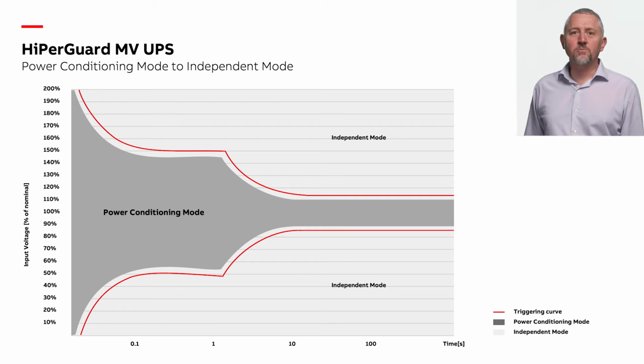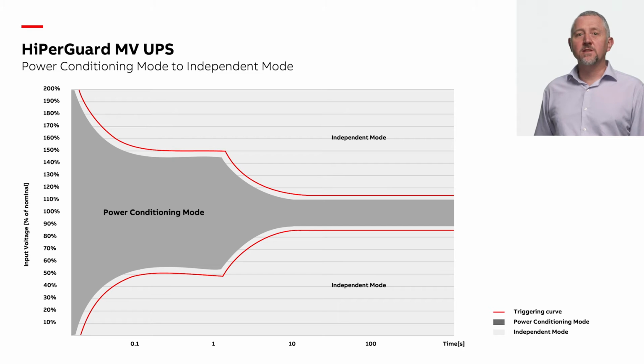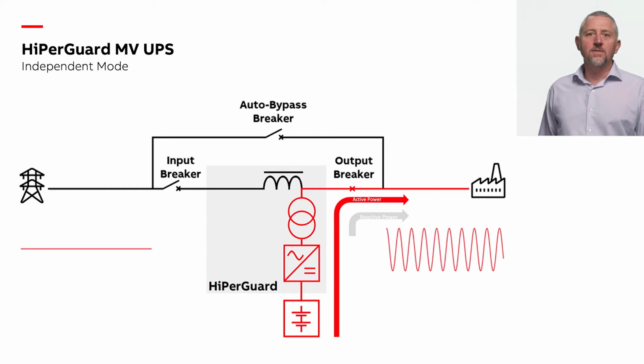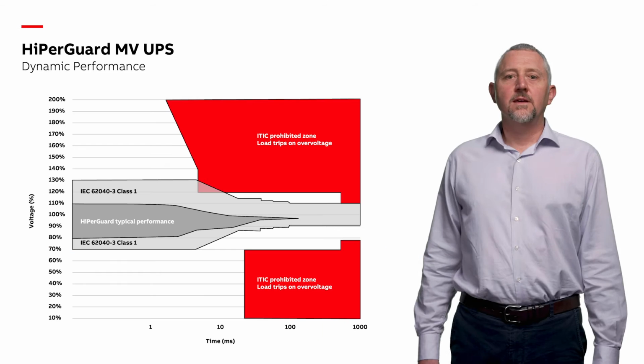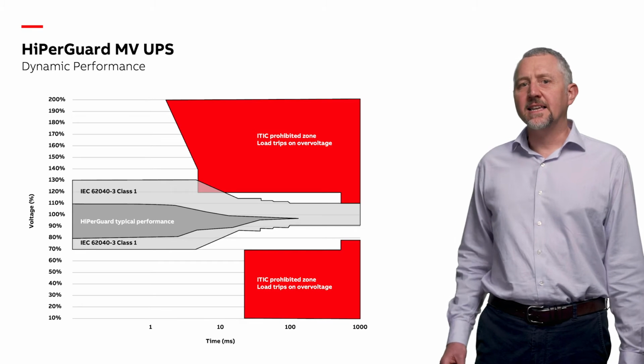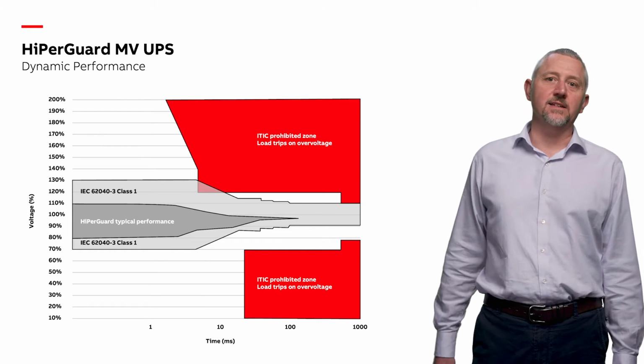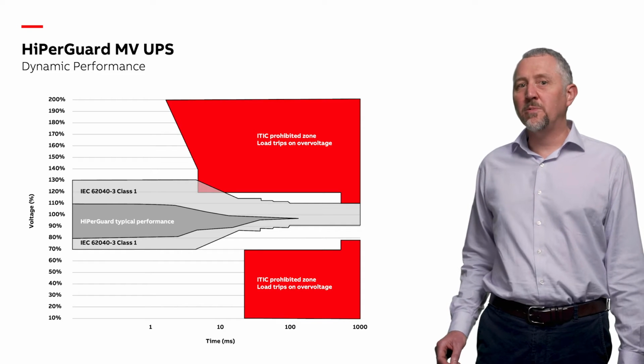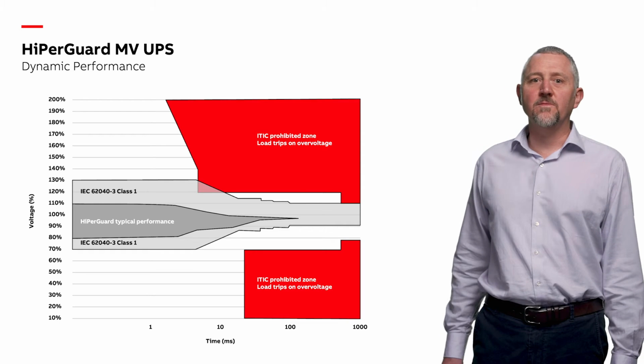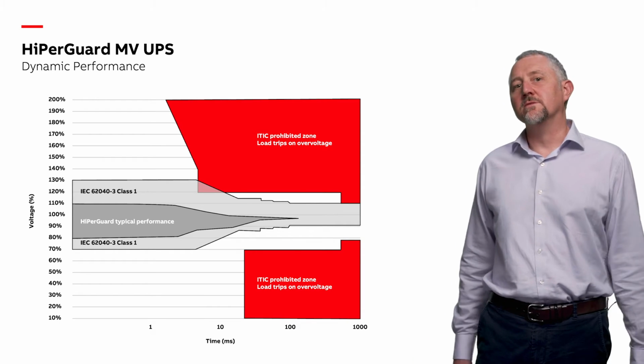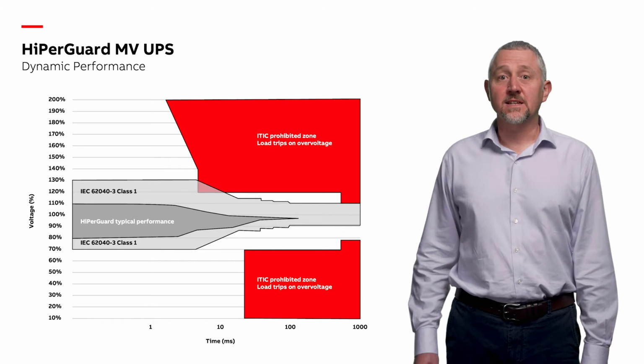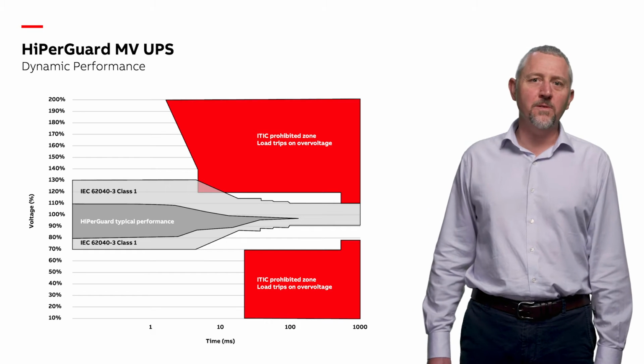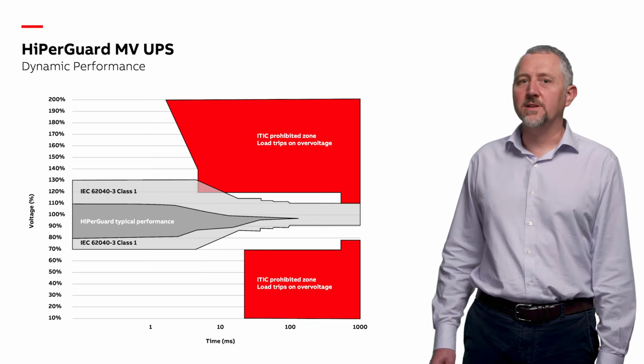Impressively, the HiPerGuard will remain in power conditioning mode for 1 second, even with the nominal input voltage sag of 50%. After the transition to independent mode, the load is fed by energy stored in the batteries. The autonomy will depend on the load level and the battery sizing. This can span from seconds to several minutes. The HiPerGuard stands out by surpassing the IEC 62040-3 Class 1 industry standard. This not only provides electrical designers with ample engineering margin, but also ensures safe headroom for voltage drops between MV output and LV loads. Examining the performance depicted in the dark grey zone on the graph reveals the HiPerGuard's output voltage over time during changes in operation mode and load steps.